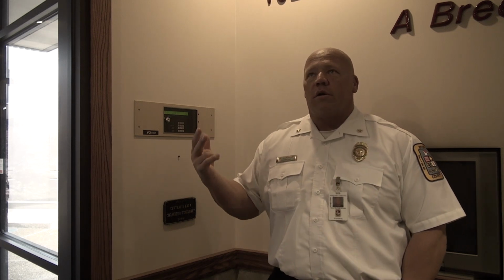Hotels, motels obviously have smoke detectors in the sleeping rooms and hallways. School buildings may or may not be required to have smoke detectors in classrooms, but they're generally in the hallways with pull stations near every exit door. And so it really depends on the classification of the building. So fire headquarters does not have that. It has pull stations and water flows.